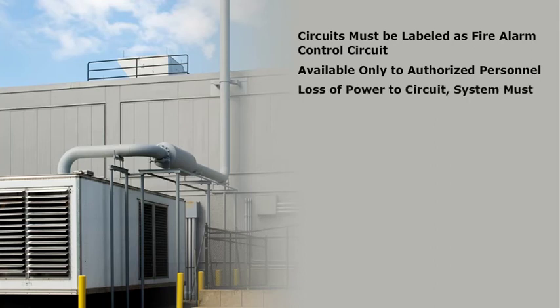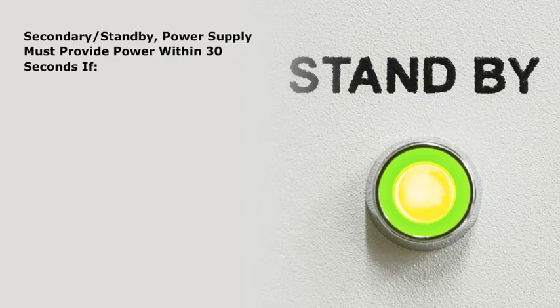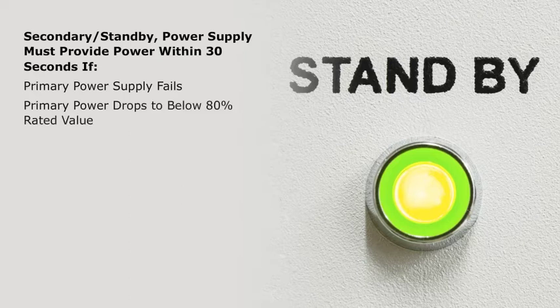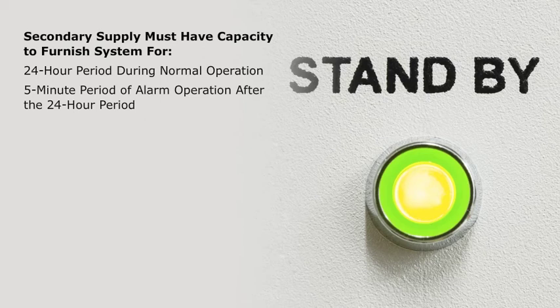In the event of loss of power to the fire alarm circuit, the system must be equipped to provide an alarm and provide notification that the power supply has been interrupted. The secondary or standby power supply must provide power to the entire electric fire alarm system within a 30-second period in the event that the primary power supply fails, or if the primary power drops to below 80% rated value. The secondary supply must have the capacity to furnish the electric fire alarm system for a 24-hour period during normal operation, and for a 5-minute period of alarm operation after the 24-hour period.